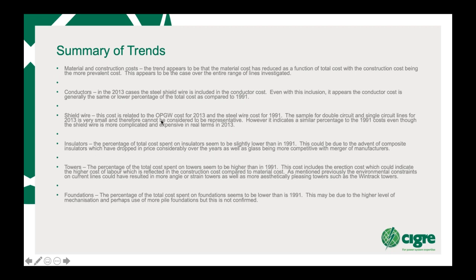The shield wire cost is related to OPGW for 2013 and steel wire for 1991. Of course, they didn't use too many OPGW in 1991. So the sample is quite small, but it does indicate a similar percentage to the 1991 costs. Insulators. The insulators are slightly lower, and the reason for that is that the composite insulator prices dropped considerably, far lower than the glass and porcelain costs. So in the past, we were using glass instead of composite because composite was quite expensive. The glass price hasn't dropped that much, but the composite price has dropped, and there's been a lot more players in the market for composite insulators.